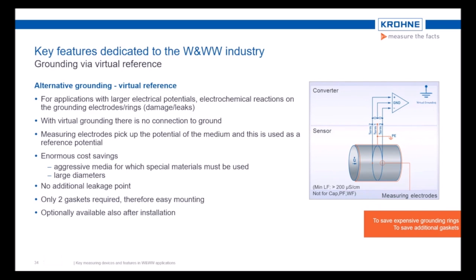To summarize all advantages of all methods and also have an additional cost saving, we can also offer the electronic grounding method virtual reference with all IFC300 converters. This grounding method is working via the normal measuring electrodes and therefore will not increase the risk for a sensor leakage. Those measuring electrodes pick up the potential of the medium, and this is used as the reference potential for the measuring.